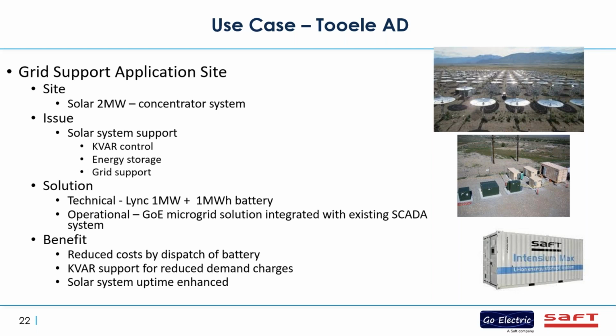So this first case study or use case is in Tooele Army Depot. And as you can see on the picture on the upper right, they have a 2 megawatt solar array, but it's a concentrator system, so a little bit different. And in this case, what the customer was looking to have was kVAR support. And we're not really the microgrid here per se. We are part of a SCADA system, and we operate to inject kVAR to help balance the entire transmission distribution system based on the operation of the solar systems. And to be able to do that, as Alex mentioned, was to be able to have that 4-quadrant control so that we can operate on the kVAR side and control the kVAR side of things as well.